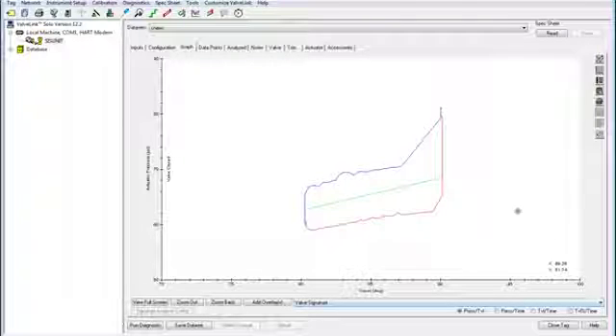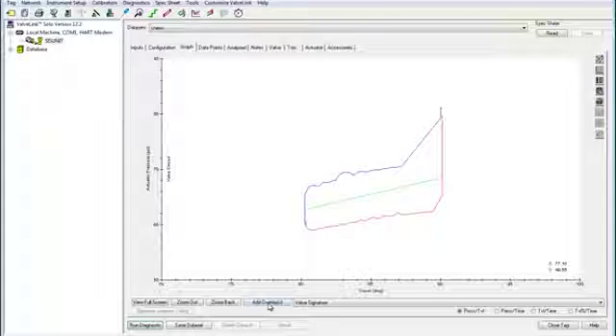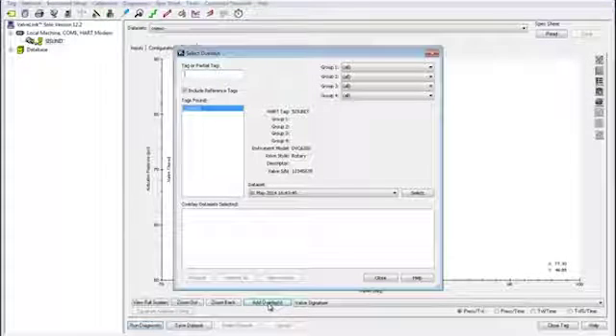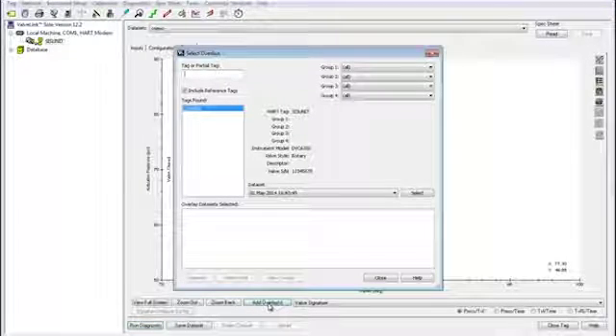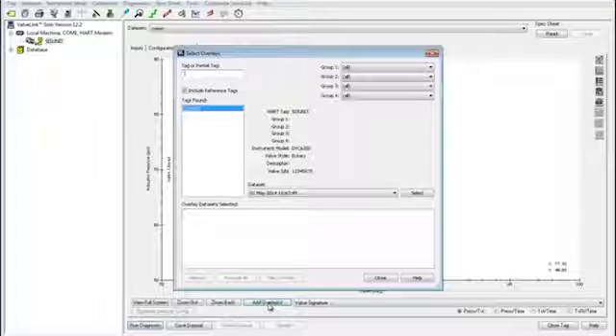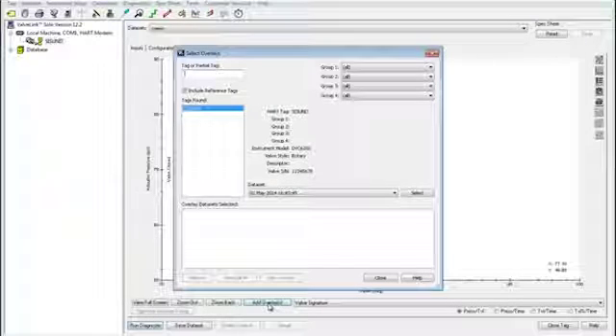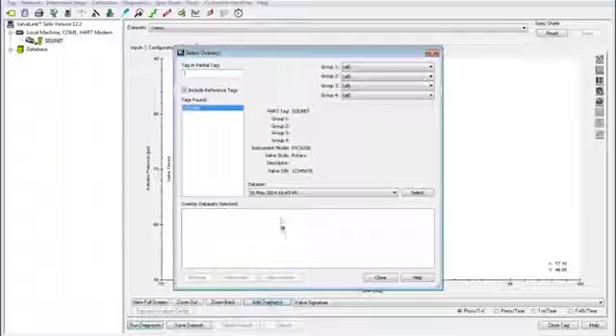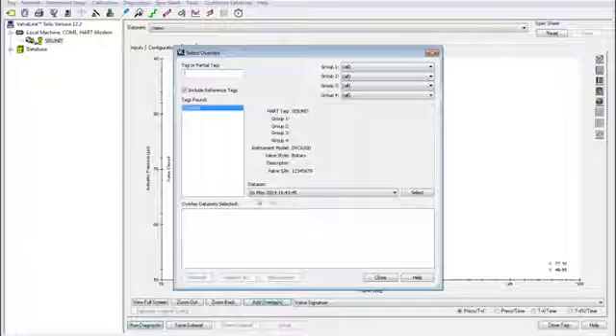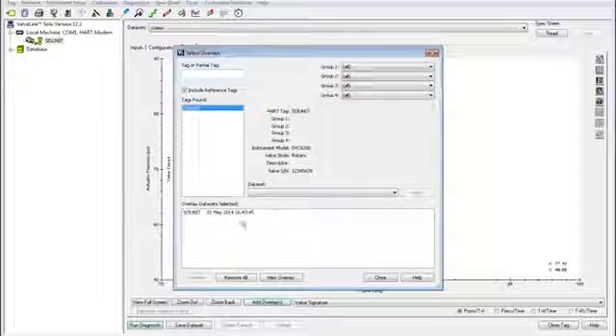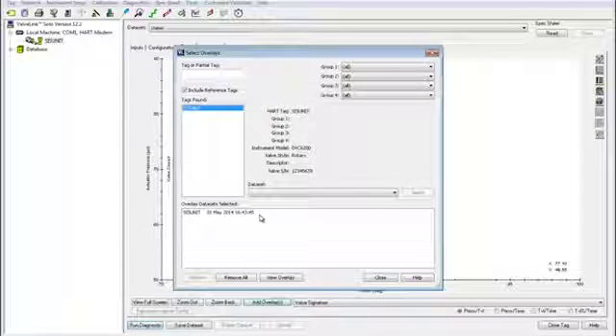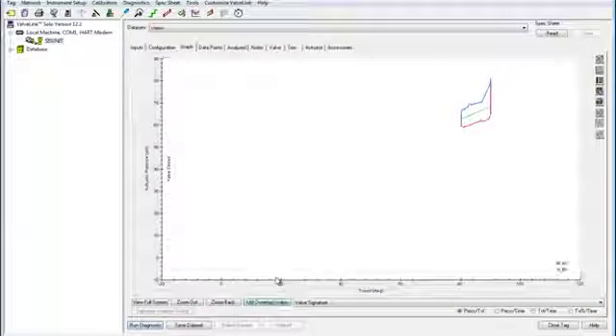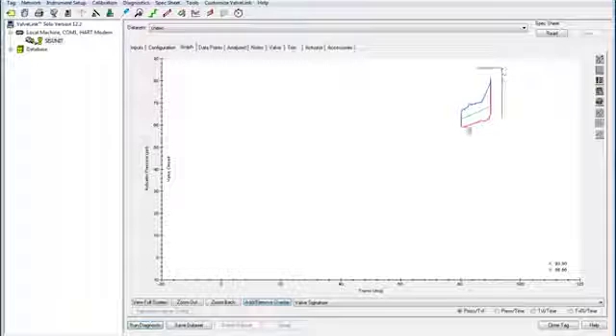Now if you want to compare your new data to your old data, click add overlays. This provides a useful visual description of how the valve may be degrading over time so that you can act proactively with your valve maintenance. Go to data set and choose a data set to compare your new data to. Click select and now click view overlay. Now you can see the overlay in the different graphs.